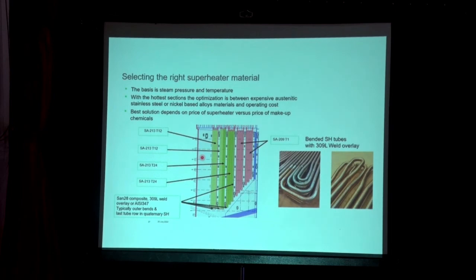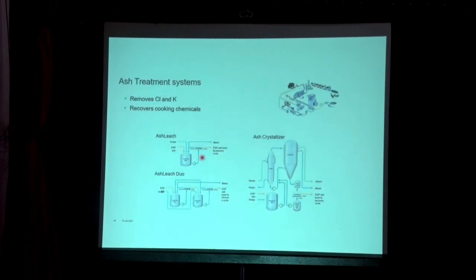In most cases, bent superheater tubes with 309L weld overlay materials are used. The ash treatment system can remove K and Cl and recover key chemicals, though there will be some sodium losses. The investment versus the chemical losses has to be carefully evaluated.